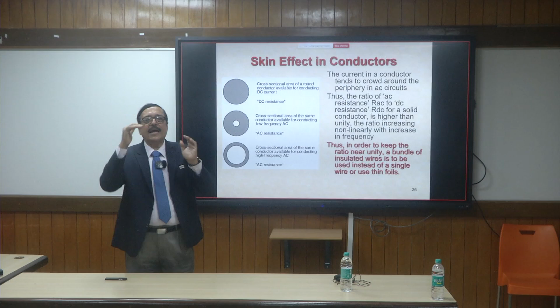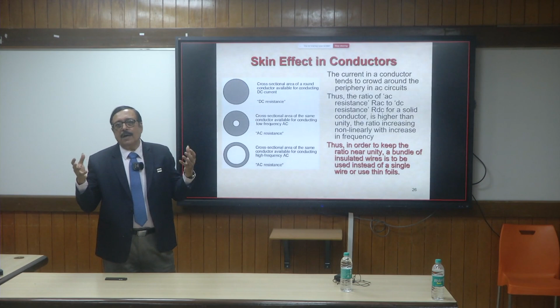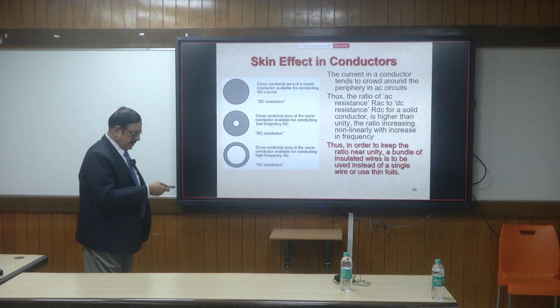Once you have foils, transposing within the foils is very cumbersome and difficult for production, because you have to take a connection out and then bring it in. It becomes too cumbersome. The overall size of the winding may exceed the size of the core. So that is a big problem in using thin foils. This gives you a rough idea on skin effect.